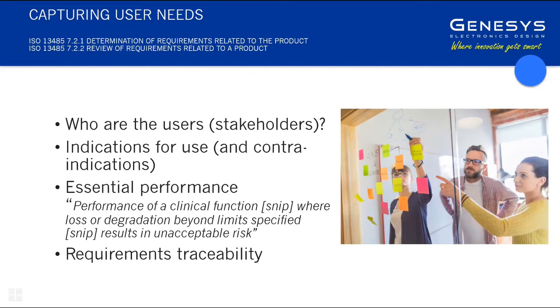Indeed. So it's essentially any aspect of the device that you, as the conceiver, designer and developer of the device, say is extremely important for the device to achieve, within a certain parametric performance range. If you think that is the case, then it's fairly likely you are considering something that's part of essential performance. And I've got the dot point requirements traceability, which I touched on before.